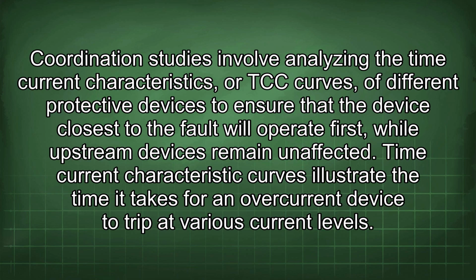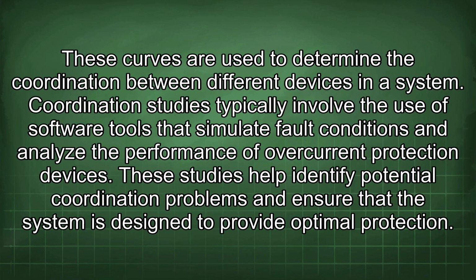Time current characteristic curves illustrate the time it takes for an overcurrent device to trip at various current levels. These curves are used to determine the coordination between different devices in a system. Coordination studies typically involve the use of software tools that simulate fault conditions and analyze the performance of overcurrent protection devices. These studies help identify potential coordination problems and ensure that the system is designed to provide optimal protection.